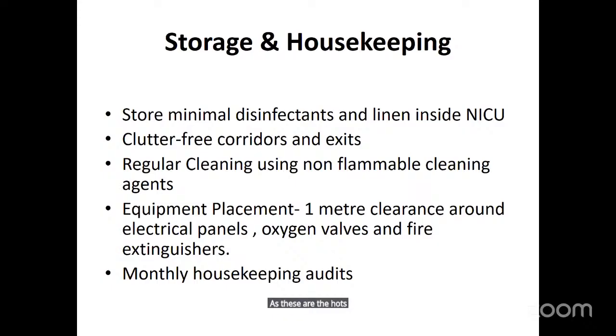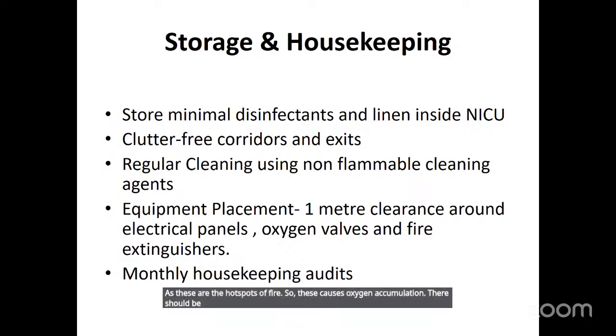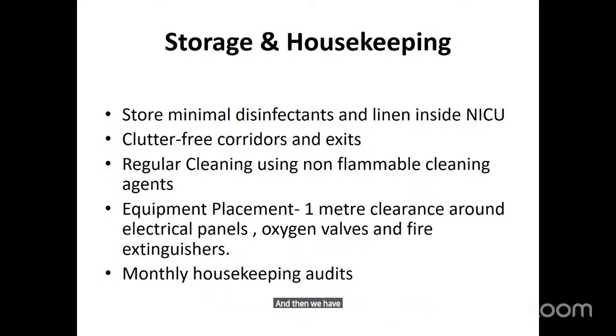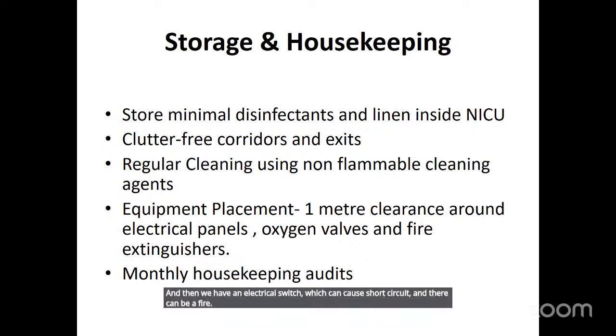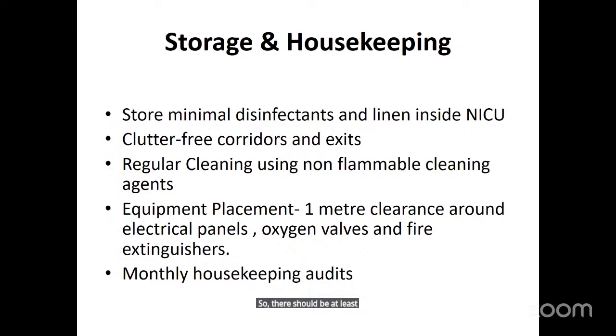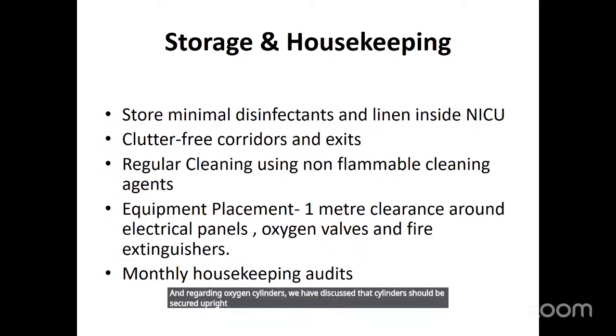of fire. So these causes oxygen accumulation. There is an oxygen accumulation near the oxygen valve, and then we have an electrical switch which can cause a short circuit, and they can be a fire. So there should be at least 1 meter clearance between them. And also monthly housekeeping audits should be done for these things. And regarding oxygen cylinders, we have discussed that cylinders should be secured upright and should be kept away from the heat source. Yeah, and good one.